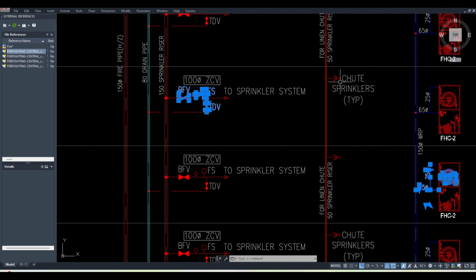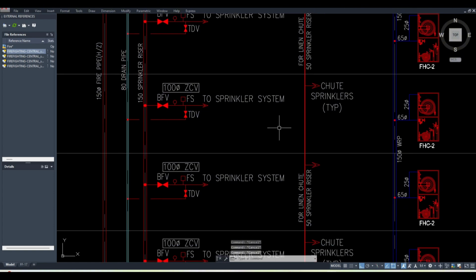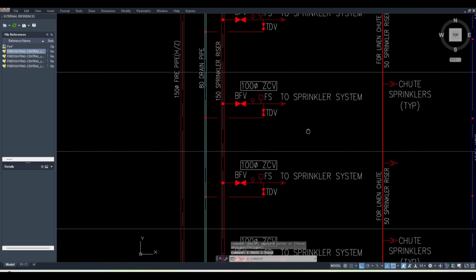Then you will go to the installation of that. Elevation-wise, your sprinkler must be 25 mm away, or not more than 300 away, from the soffit. Within that range your sprinkler must be there. Then suppose you are providing a sprinkler, and in between there is any duct or any item which is bigger than 1200 mm wide. Then you must provide a sprinkler below this item also. Even if you have provided one above, you also need to cover this area below. So that requirement is also there.